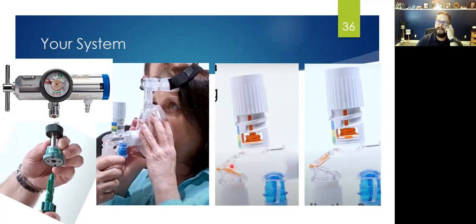And in this case, that could be a sign if they somehow were over breathing this or any other device, if the anti-asphyxia valve drops, even flutters down during their exhale or their inhalation, they're probably over breathing that device because the device isn't providing the flow that they need. And in this picture, you can see that the anti-asphyxia valve is up and that the flow is coming in, and they're actually exhaling. You can see that this pressure, the exhaled air, is creating this to open up and allow that to go out.